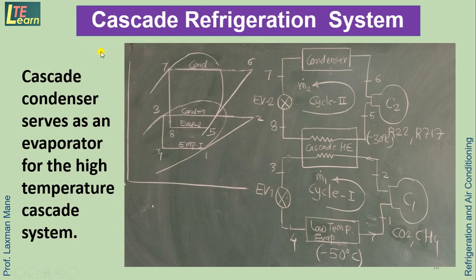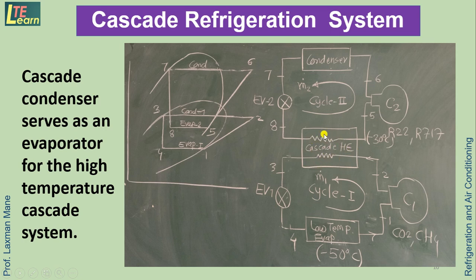The next type of multi-pressure system is the cascade refrigeration system. In this system, two vapor compression cycles are combined: the condenser line (2-3) of the low-temperature VCC is connected to the evaporator line of the high-temperature VCC. This combined heat exchanger is called the cascade condenser. It serves as a condenser for the low-temperature cycle and as an evaporator for the high-temperature cycle.